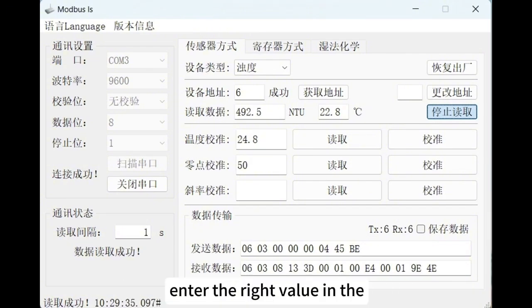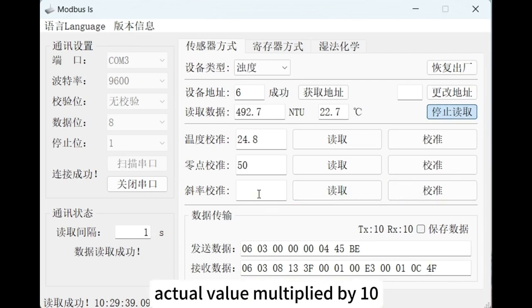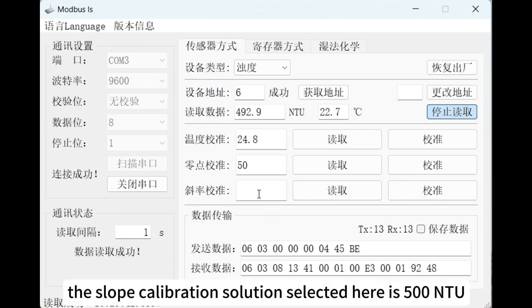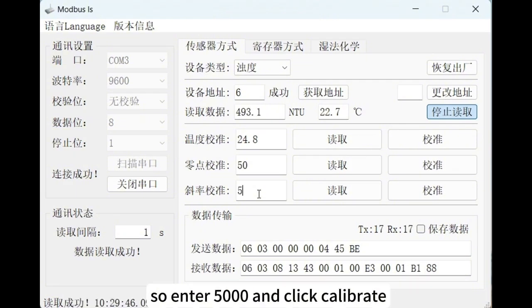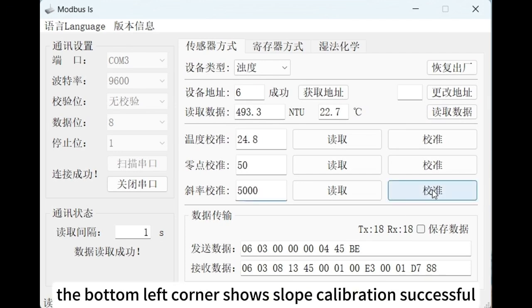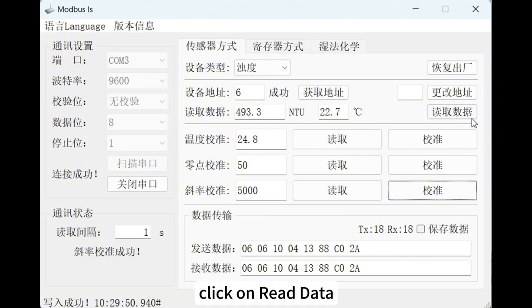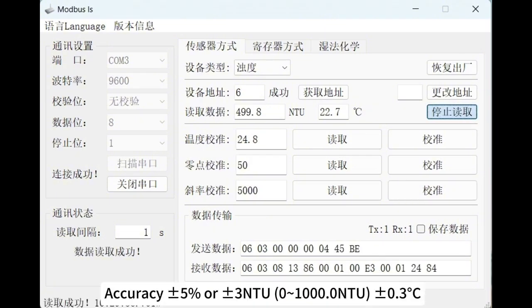Enter the right value in the slope calibration right box. The right value is equal to the actual value multiplied by 10. The slope calibration solution selected here is 500 NTU, so enter 5000 and click Calibrate. The bottom left corner shows slope calibration successful. Click on Read Data. The turbidity slope calibration is complete.